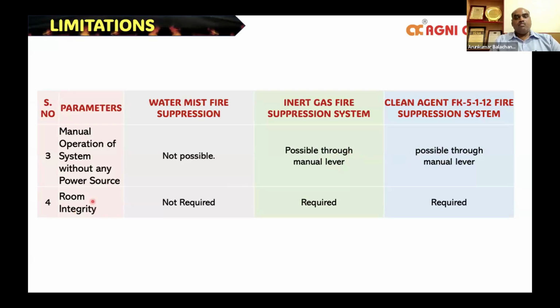And finally, the more important, room integrity. For an inert system, as well as for a clean agent system, we need proper room integrity, and also to ensure that 85% of the design concentration is there for 10 minutes so that reoccurrence of fire is not happening. But for a water system, that is not required. It can be used in any type of room, and we don't need room integrity.